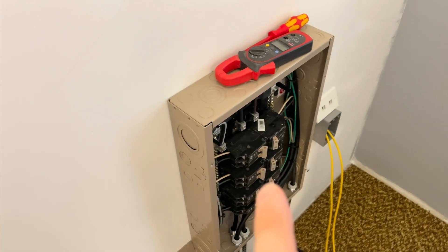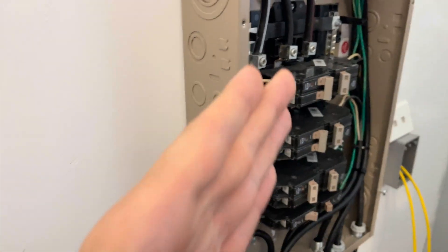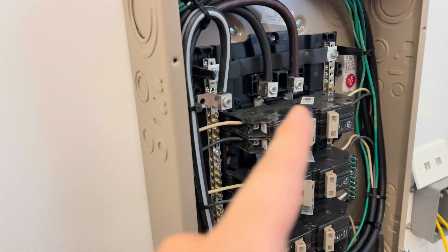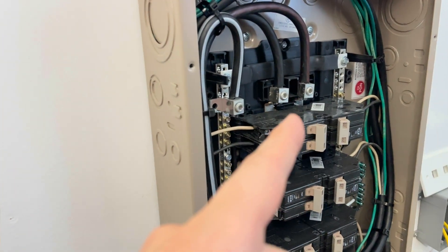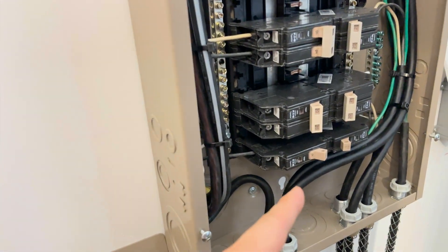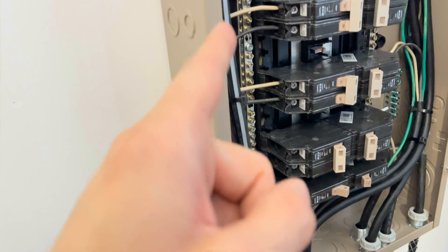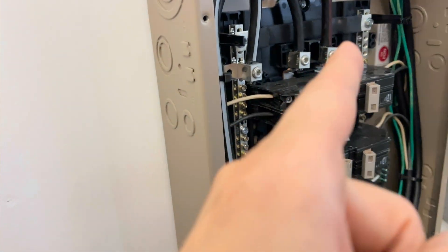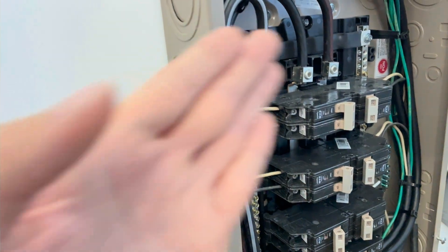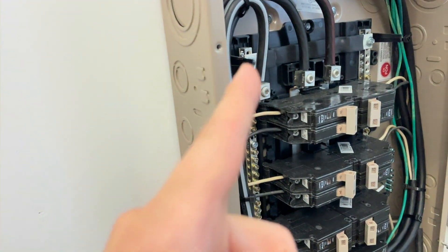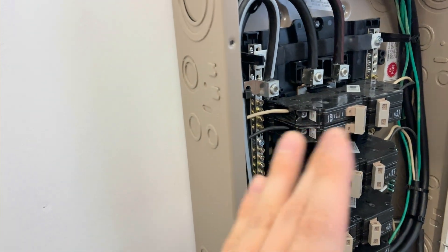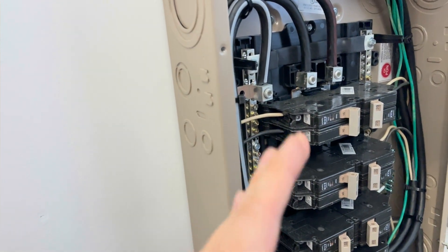And now the power supplies are typically more efficient when run at 240 volts. So if you're in North America, you very likely have 240 volts present in what's called split phase service. So there's two phases, effectively, and a 120 volt circuit is powered off one leg and it goes to neutral. The 240 volt circuit is powered off both legs and doesn't use the neutral. It's basically a 240 volt service with a neutral center tap conductor. So technically, all North America is actually 240 volts, but people call it 120 because that's what's present at your outlets.